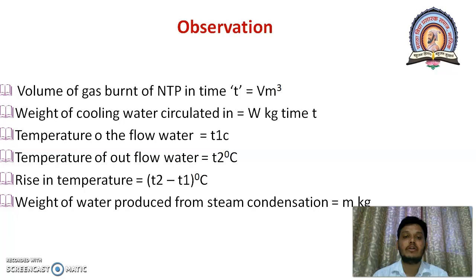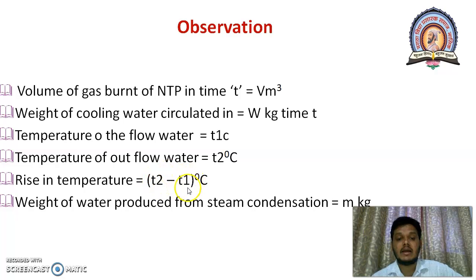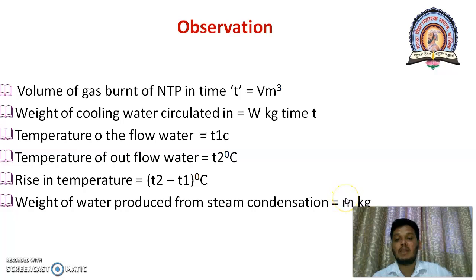Which observations are recorded in the Boys gas calorimeter? The first observation is the volume of gaseous fuel burned at standard temperature and pressure condition — V meter cube. The second observation is the weight of cooling water circulated in the calorimeter, which is in kilograms. Then, temperature of inlet water T1 degree Celsius. Temperature of outlet water T2 degree Celsius. Rise in temperature means T2 minus T1 degree Celsius. And the weight of water collected by steam condensation, denoted by small m, also in kilograms.